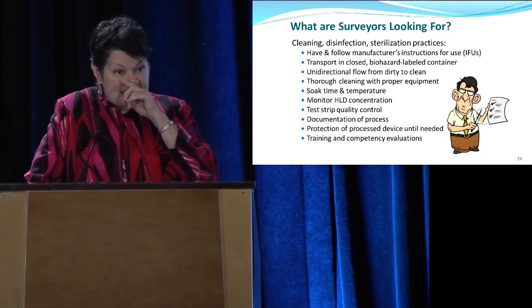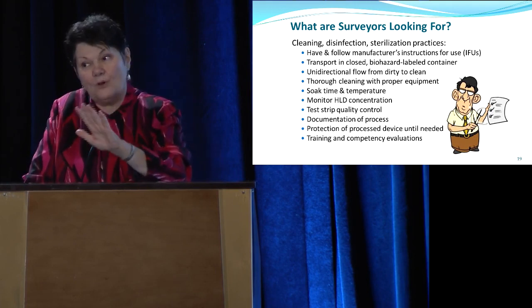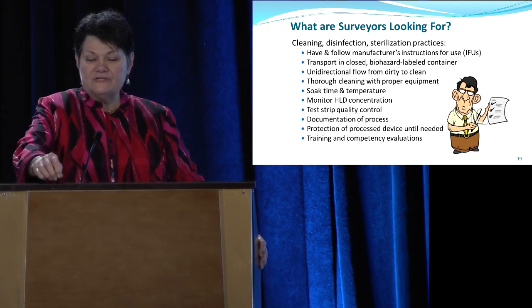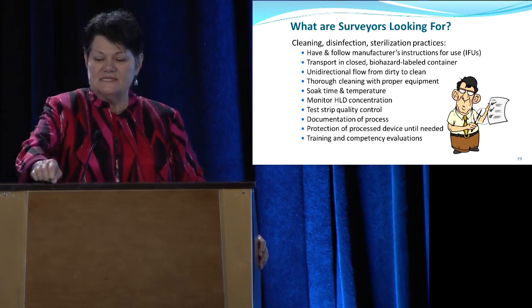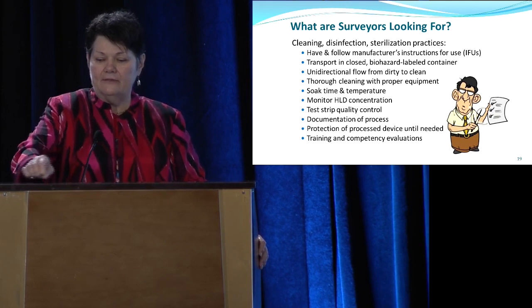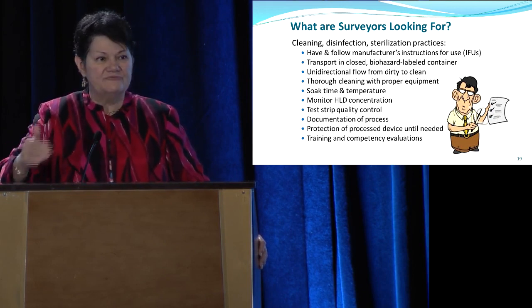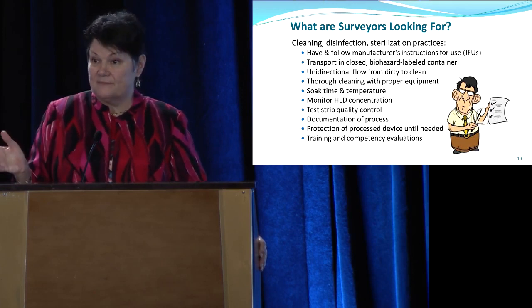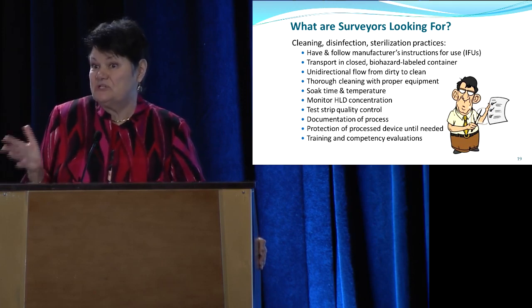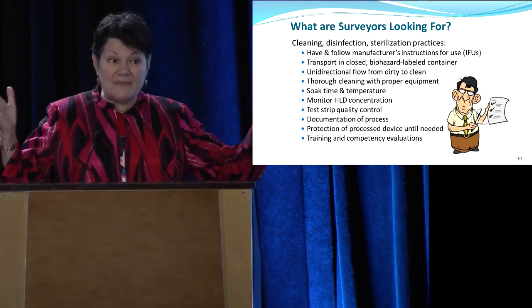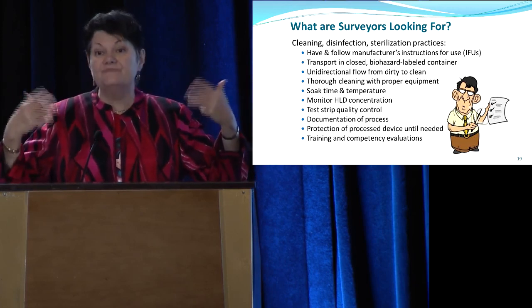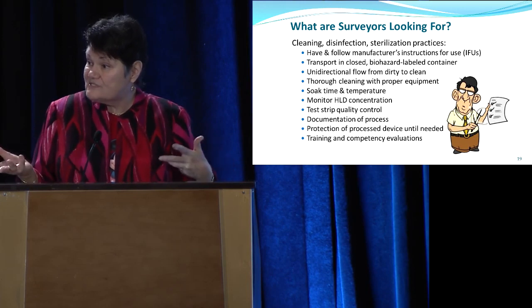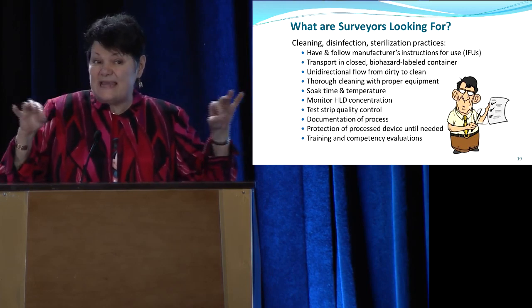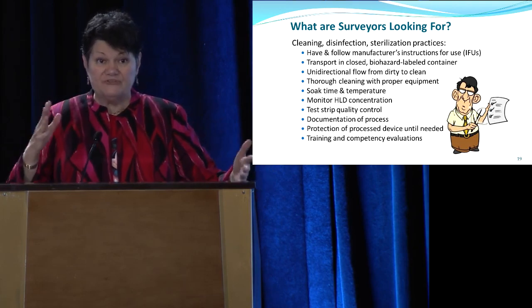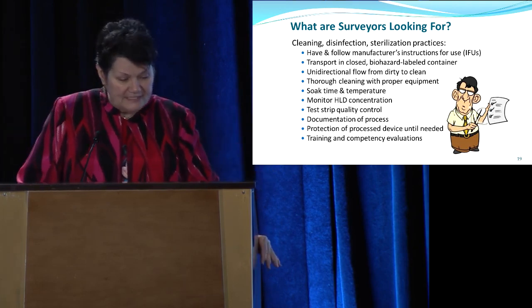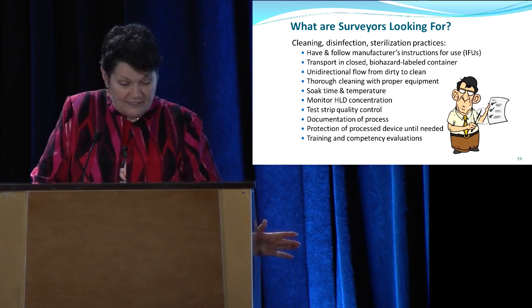The other thing I've seen with not sonographers, but with techs, is they very dutifully write down the MEC, fail, fail, fail, fail, fail, day after day after day. They were told to record it, not that there was something special they had to do, like change the solution. I'm serious, you can't make this stuff up. So you need to be sure if you've got people working for you who do some of those tasks, that they get it, that they understand if it's failed, this is what you have to do, or at least come get me and I'll tell you what you need to do. You can't make this stuff up.